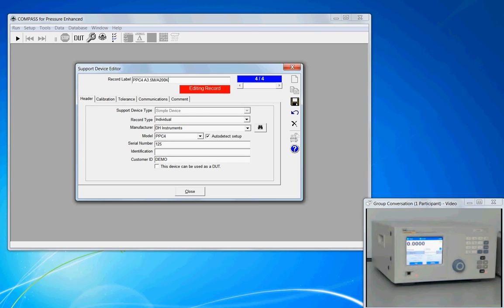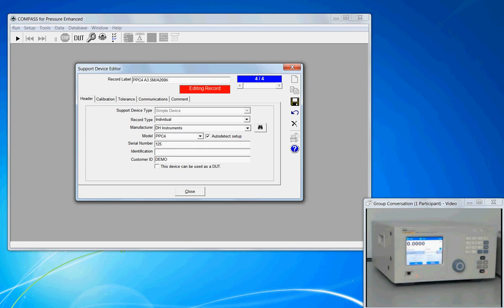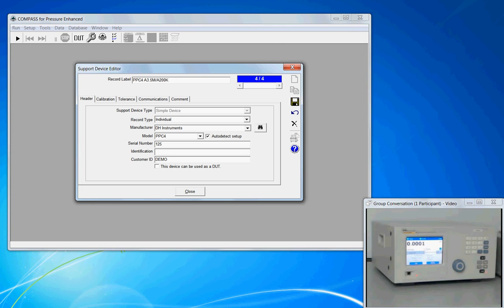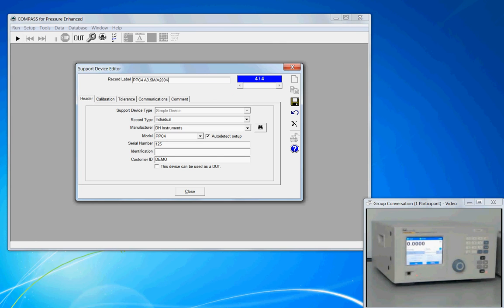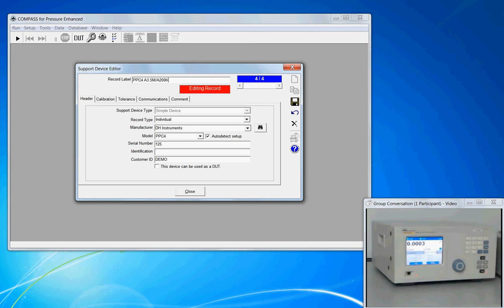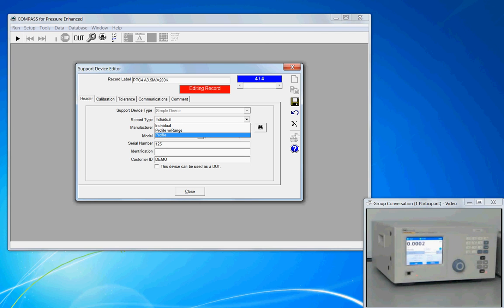So on the header tab, this is the top-level information about manufacturer, model, serial number, and owner. But we have a record type, and it's one of a kind. It's an individual. If I had multiple PPC-4s that were very similar in pressure range, I might want to elect to go with a profile.